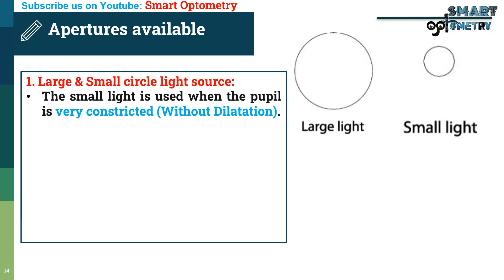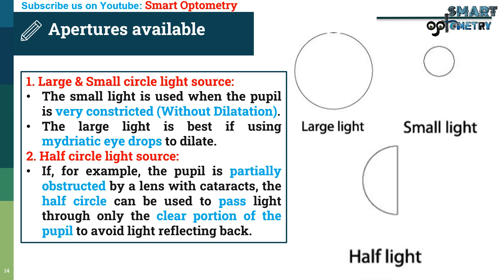Apertures available in the ophthalmoscope: 1. Large and small circle light source. The small circle light source is used when the pupil is very constricted or when examining the patient's fundus without dilation. The large circle light source is best when using mydriatic eye drops to dilate the pupil. 2. Half circle light source: if the pupil is partially obstructed by a lens with cataracts, the half circle can be used to pass light through only the clear portion of the pupil to avoid light reflecting back.